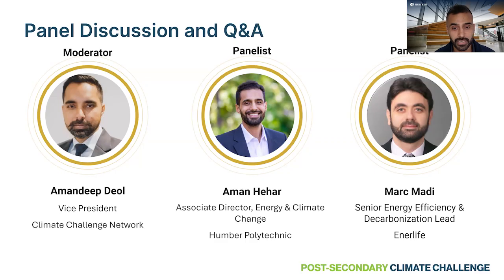You touched on it during your presentation. Schedules are really important, that's a fast and easy one. Setting up schedules to have systems turn off overnight, weekends, those are the obvious ones. But what about stat holidays? What about other times the campus is closed? For example, at Humber we shut down between Christmas and New Year's, a full week when we don't have to deliver the same level of thermal comfort. So there are opportunities around schedules. You just got to go in there and look, and it's worth revisiting on a periodic cycle.